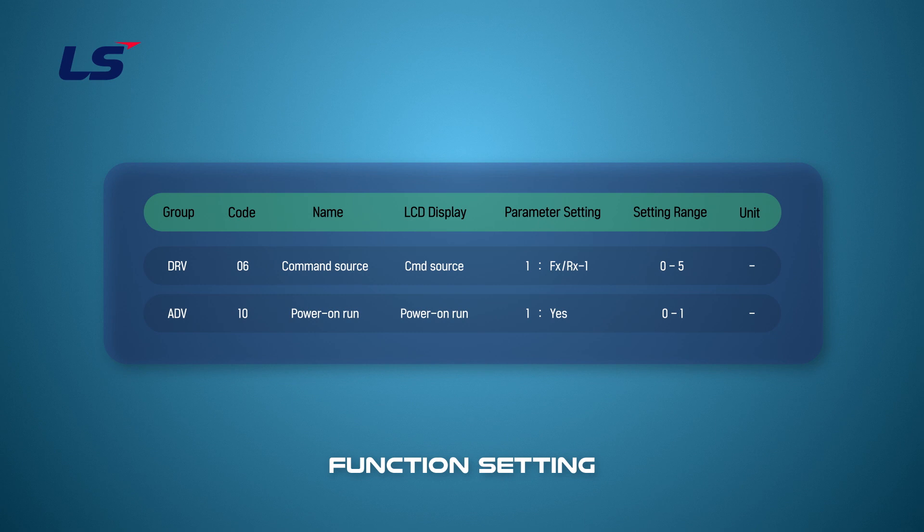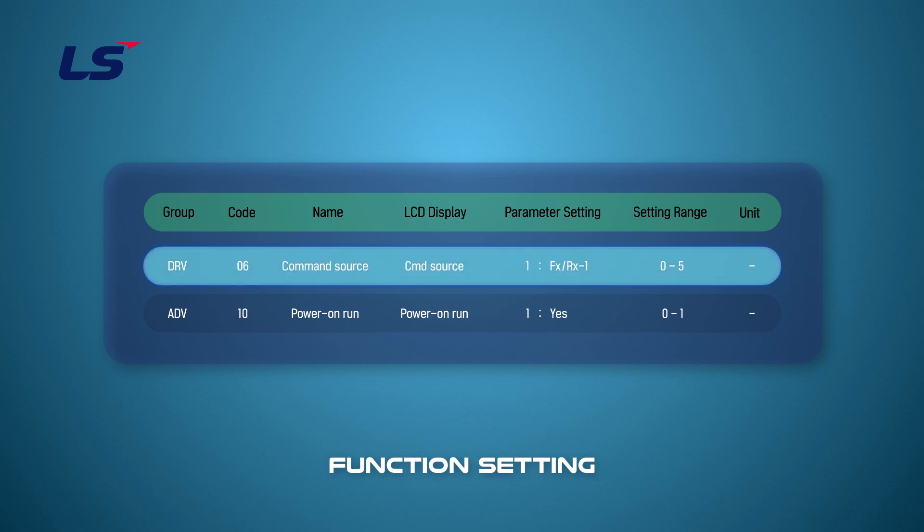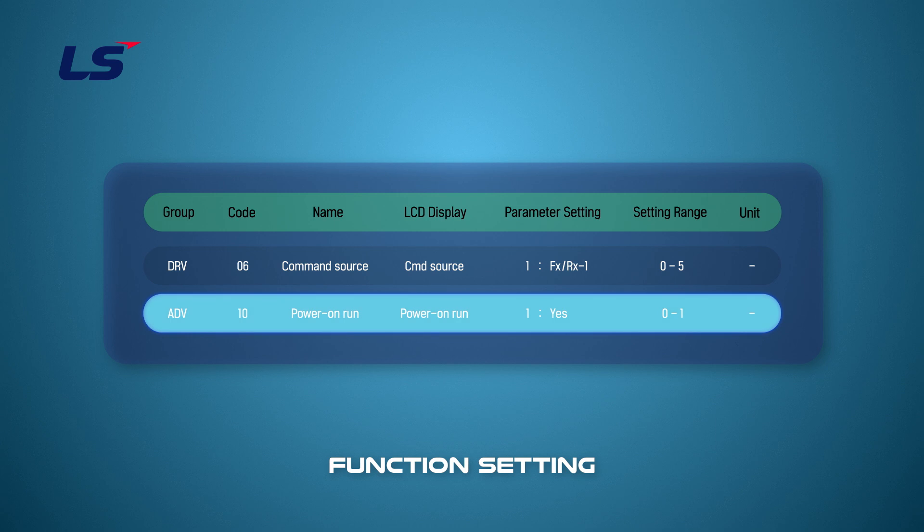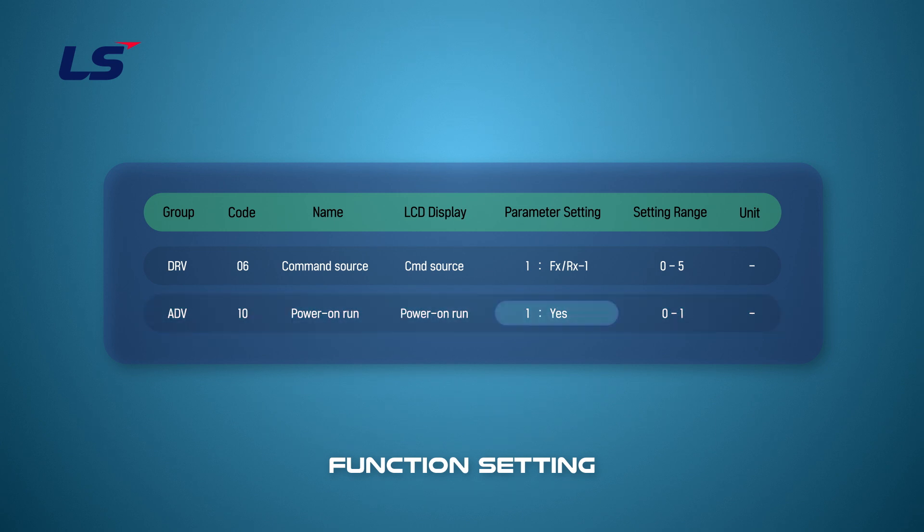To use the Power On Run function on iS7, set DRV6 command source to FXRX1, and set parameter ADV10 to YES to activate the Power On Run function.